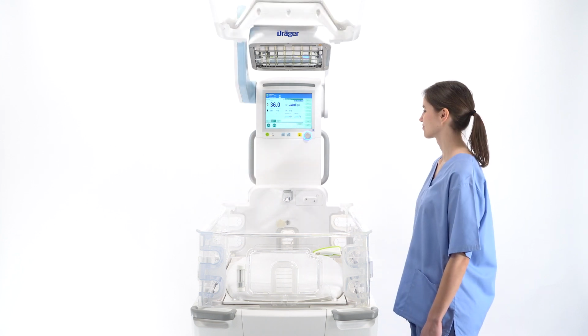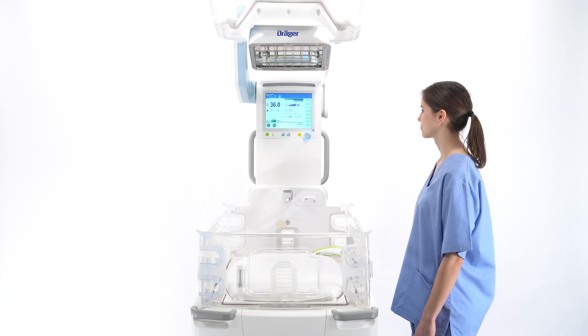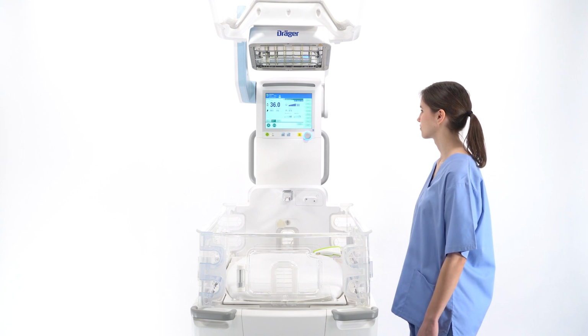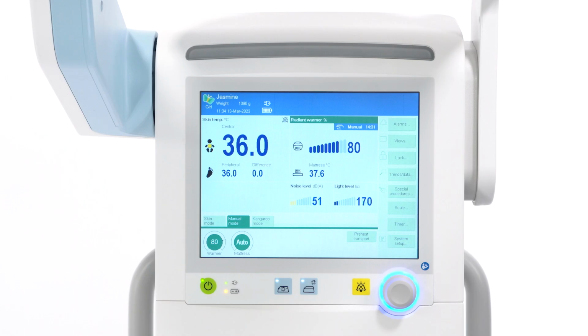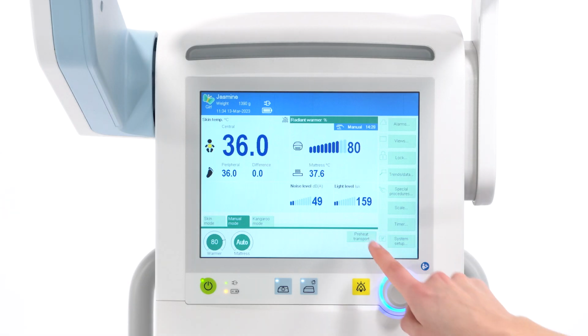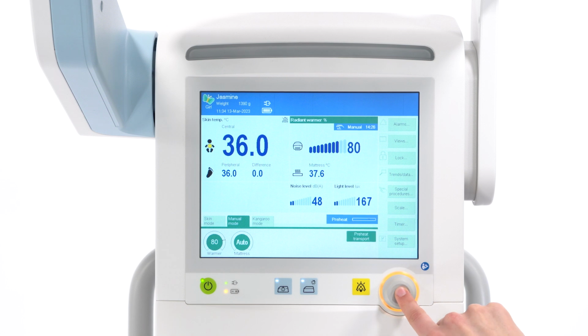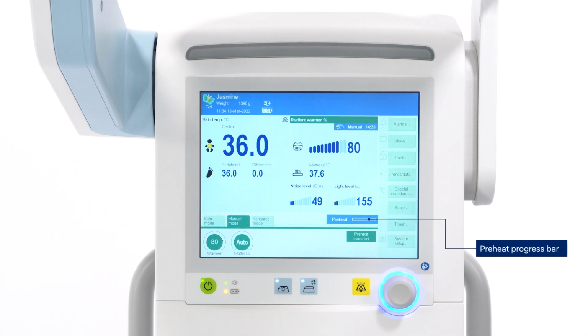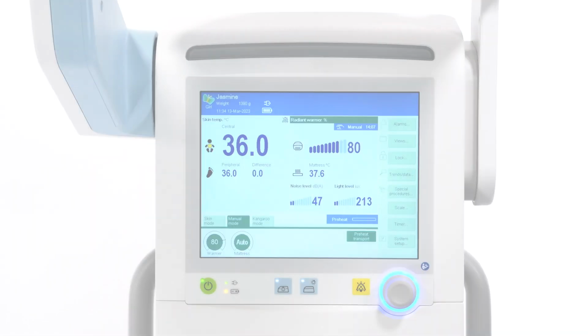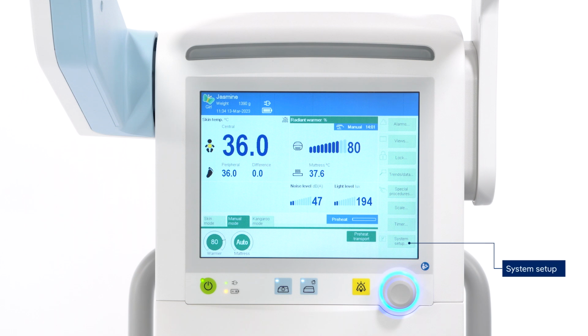If the device is in radiant warmer operation, for example during initial care in the labor delivery unit, the convective heater can be preheated while the hood is open. Press Preheat for transport and confirm with the rotary knob. A progress bar is displayed and shows the status of the convective heater. When the progress bar is completely full, the requested air temperature will be reached during transport. It takes approximately 20 minutes to fill the progress bar, and the progress bar continues to be displayed after the hood is closed. The preheat for transport temperature can be set via System Setup under Therapy.